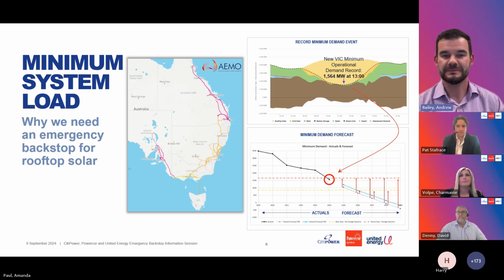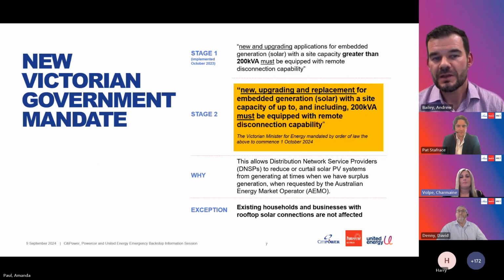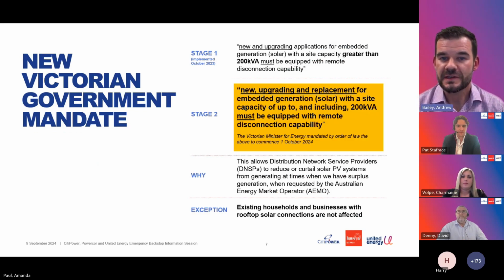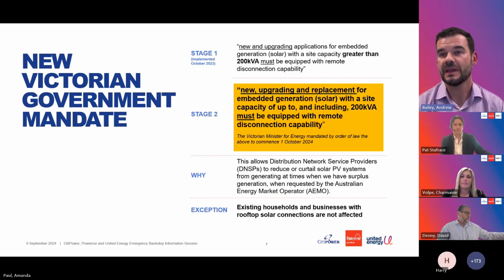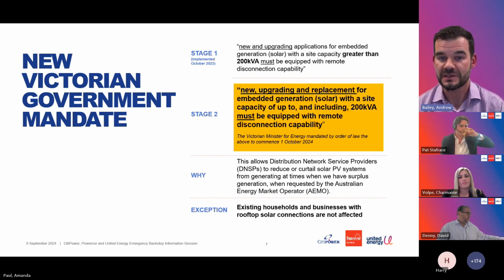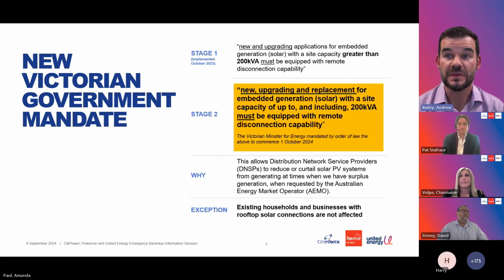The Victorian government has introduced the emergency backstop in two stages. Stage 1 applied to systems greater than 200 kVA, and that was introduced in October last year. Stage 2 applies from the 1st of October this year, and it applies to all new, upgraded and replacement rooftop solar systems, which must be emergency backstop enabled. Note that it does not apply to existing rooftop solar systems.